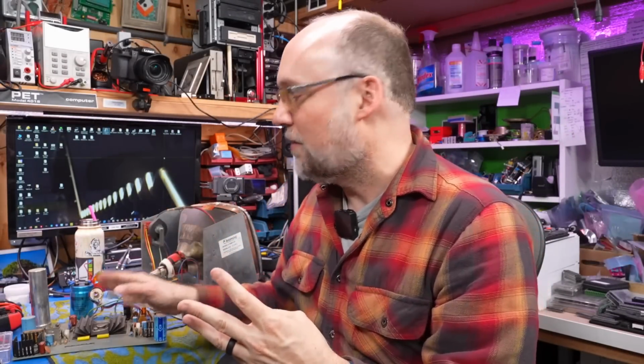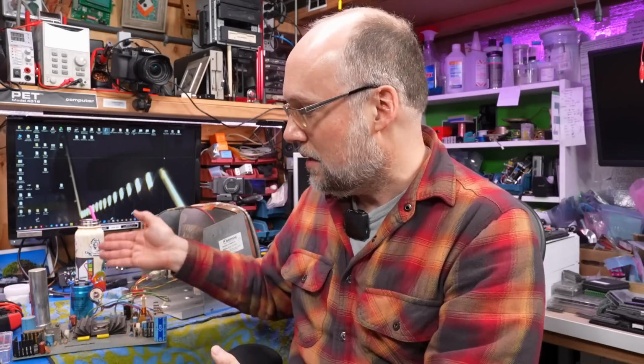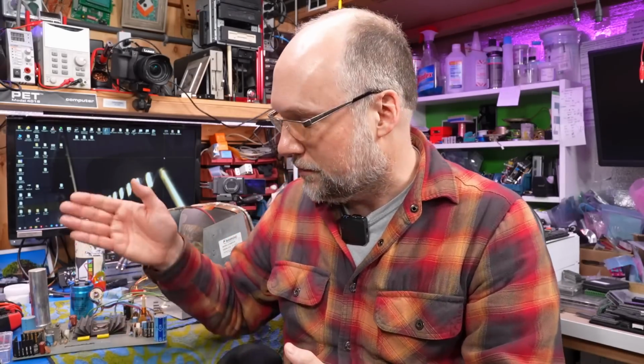The three windings in that transformer mean one of them could have failed, like the one that goes to the 5-volt rail here, which carries the most current. If that sent 120 volts or some higher voltage into this rectification circuit, it might have exacerbated or caused that flashover we see, and it could have damaged parts of this board, or if the 5-volt regulator shorted, it could have gone through to the motherboard and caused massive damage there.